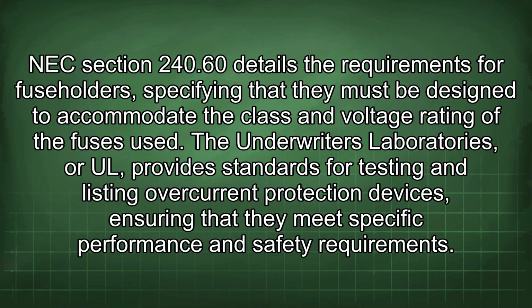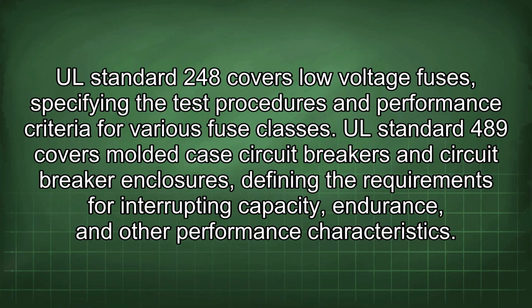Underwriters Laboratories, or UL, provides standards for testing and listing overcurrent protection devices, ensuring that they meet specific performance and safety requirements. UL Standard 248 covers low-voltage fuses, specifying the test procedures and performance criteria for various fuse classes. UL Standard 489 covers molded case circuit breakers and circuit breaker enclosures, defining the requirements for interrupting capacity, endurance, and other performance characteristics.